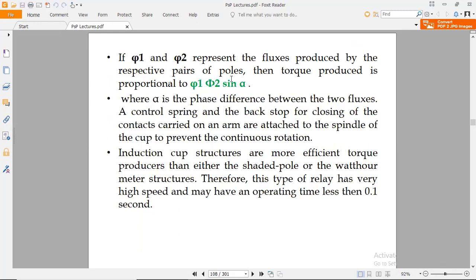They represent the fluxes produced by the respective pairs of poles. Then the torque produced is proportional to phi 1 times phi 2 times sine alpha. It is a combination derived from this relation, where alpha is the phase difference between the two fluxes of the coils. The difference of phase angle between phi 1 and phi 2 is called alpha. A control spring and a back stop for closing of the contacts carried on an arm are attached to the spindle of the cup to prevent continuous rotation. So the cup rotates, and the continuous rotation would be formed.